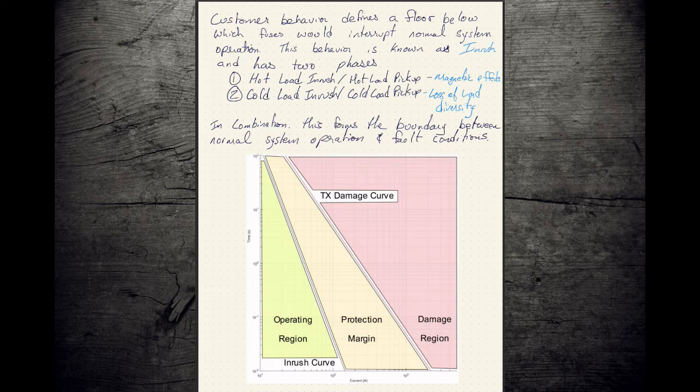And then after that's all resolved, you still could be in a situation where you've lost all your load diversity. And now you have some serious overloads while that load diversity gets reestablished. Think about a long power outage on a hot summer day, and you turn the power back on, and everybody's air conditioner and everybody's fridge and everybody's freezer and everybody's everything all wants to run at once instead of taking their time and cycling through things.